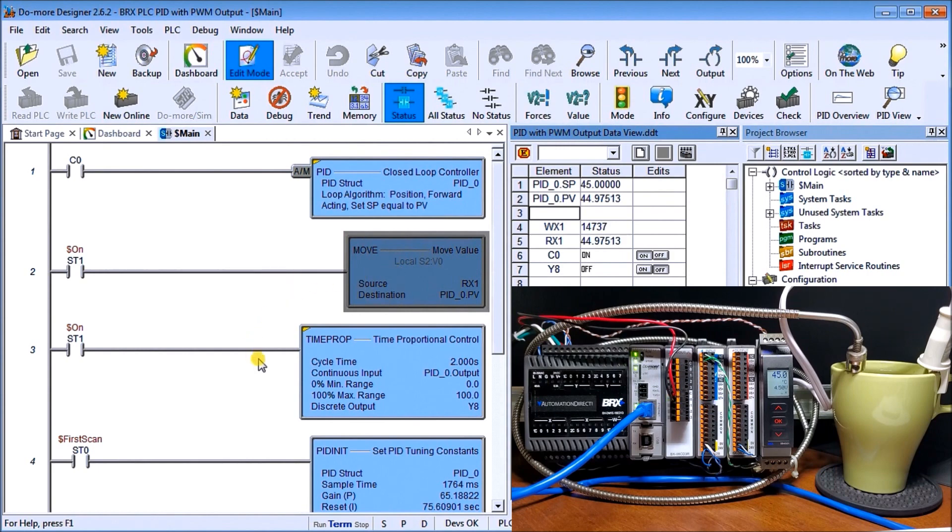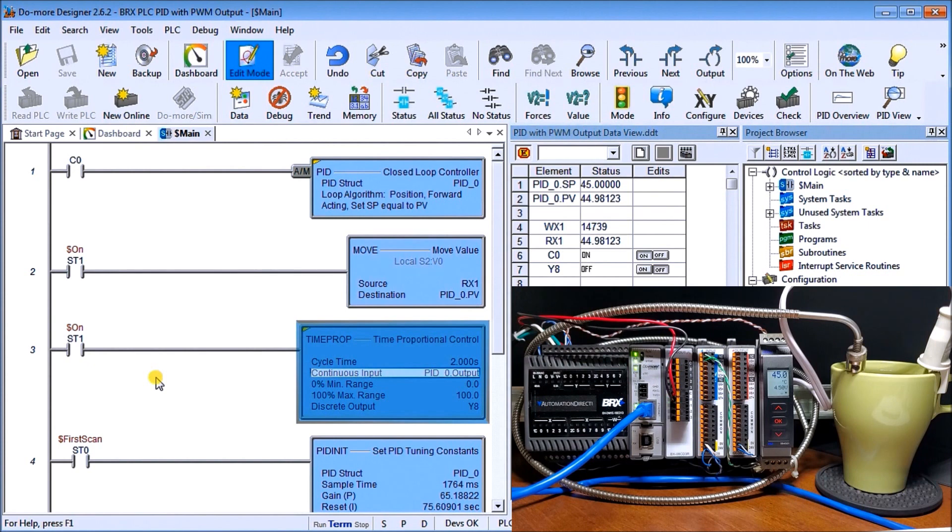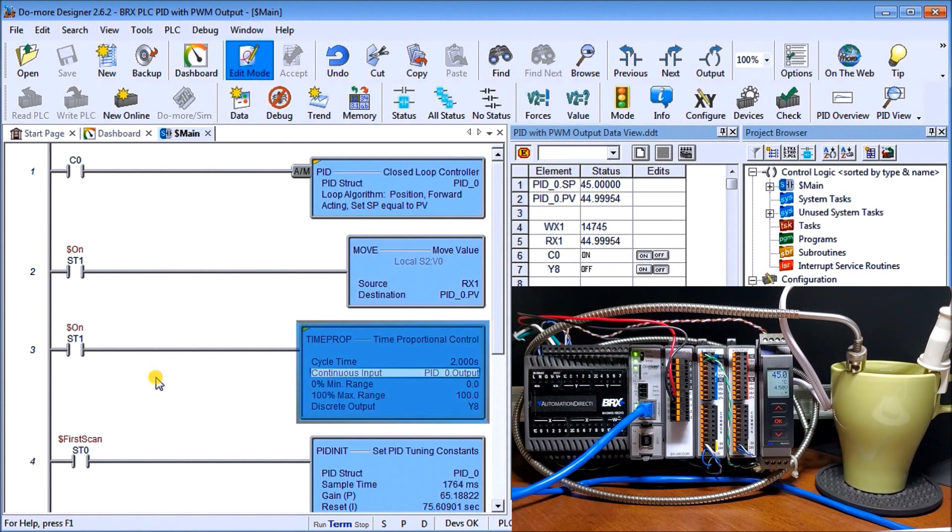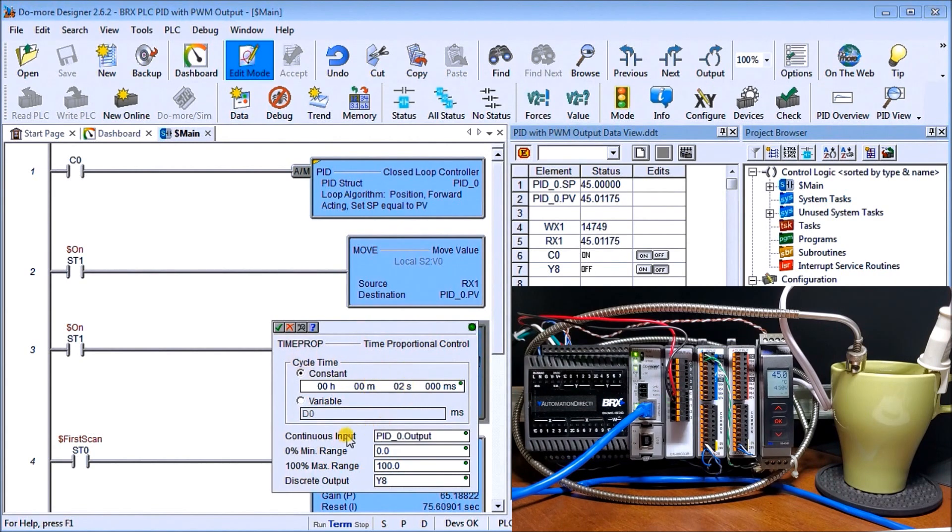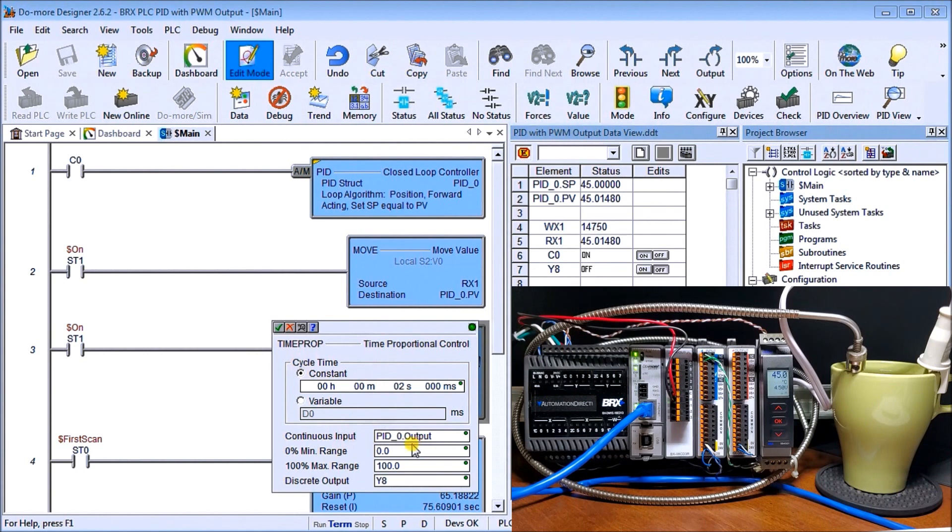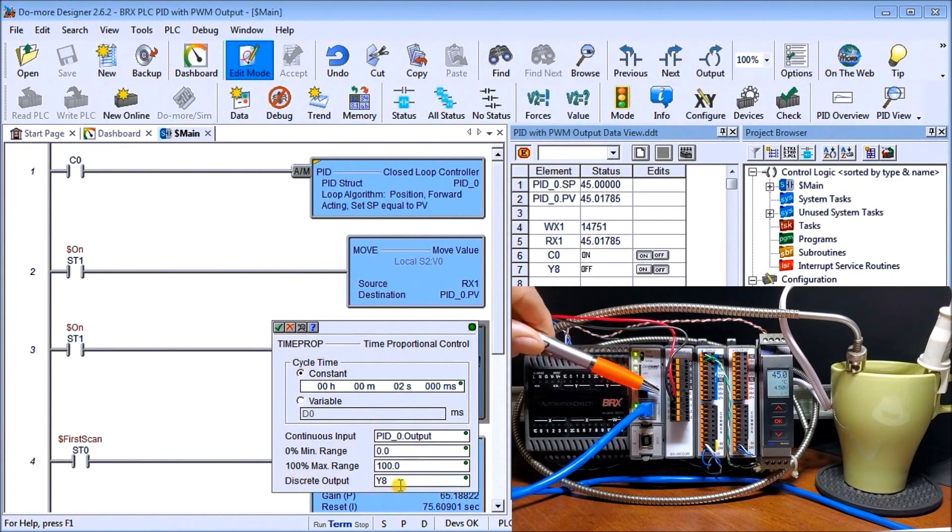We have a relay output that's controlling the immersion heater, and that relay output we want PWM or pulse width modulated. Because it's going to be relatively slow, we're going to use time proportional output. We have a cycle time of two seconds. Our continuous input comes from our PID loop zero output, and that output goes from zero to 100. We're turning on our discrete output Y8.